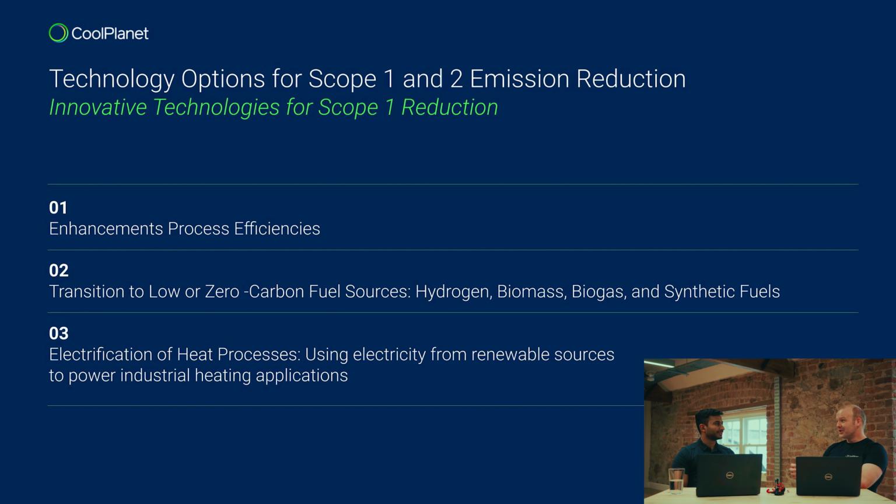So you don't even get the full value, as opposed to a heat pump, where you put in one piece of energy and you may be getting 4 to 5 times out in delivered heat. So from that point of view, as a pure energy requirement to deliver your operations, it's a great thing to reduce energy. As we'll see later on in the masterclass, there are barriers around that, because maybe the cost of electricity versus the thermal fuel that you're using may not be in a commercial favour. But from a pure energy point of view, heat pumps allow for that.